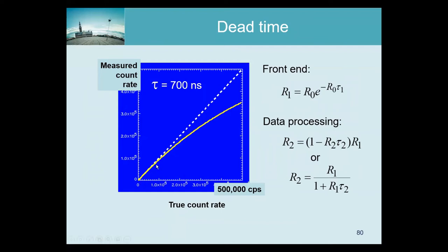An even better way to think about it is with increasing activity. In the beginning the gamma camera nicely keeps up — you double the activity and the camera reports twice the activity — but if you go higher and higher it starts having a problem counting. The reason is that every now and then two photons arrive at the same time, their energies are added, and the energy window rejects this combined photon because it doesn't have the right energy.